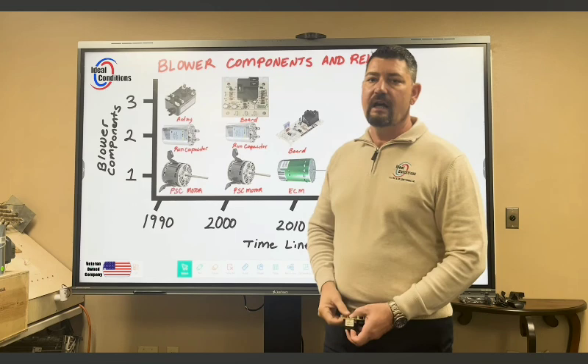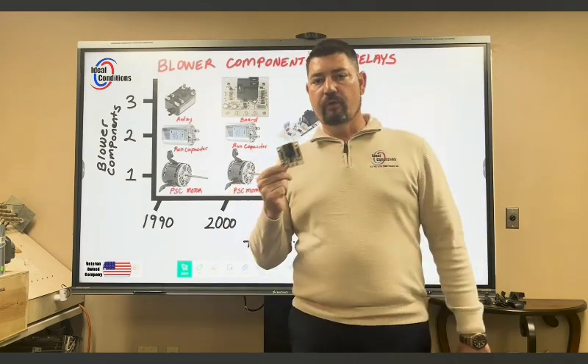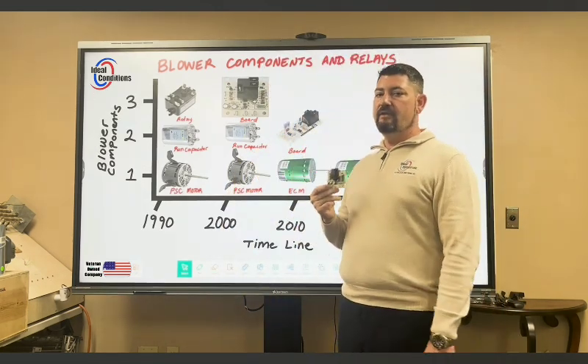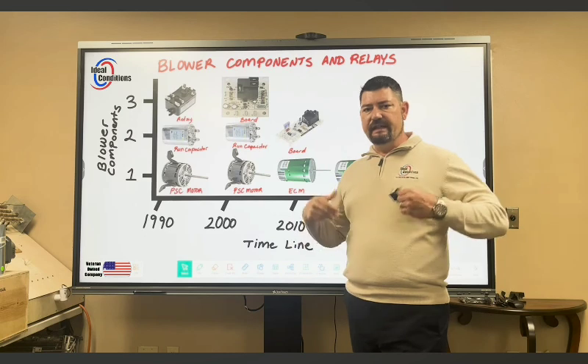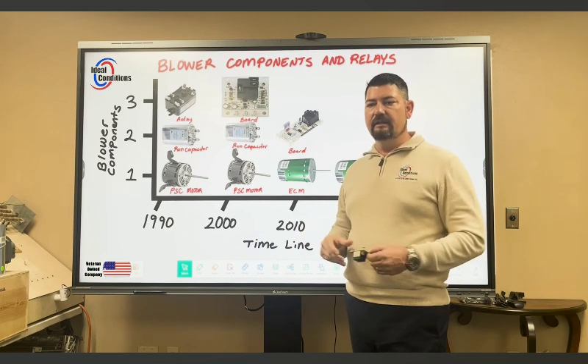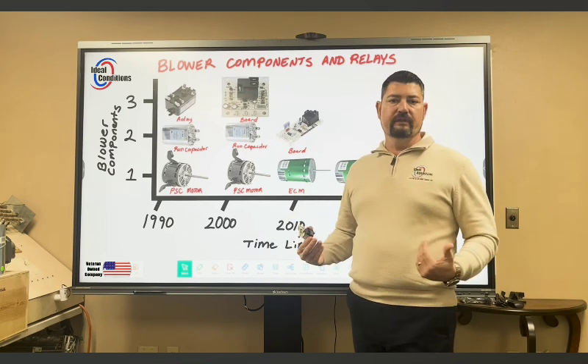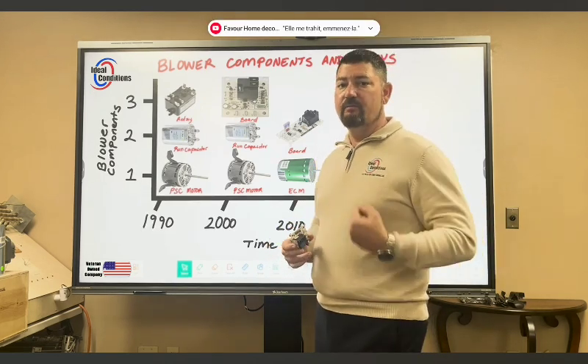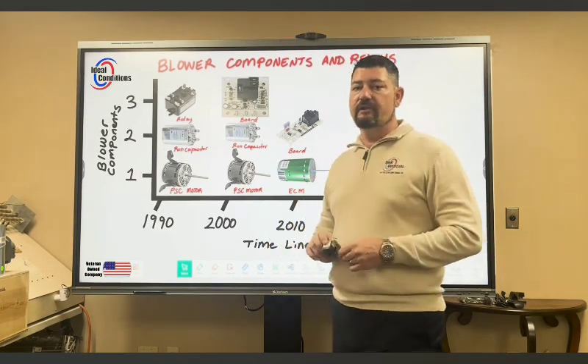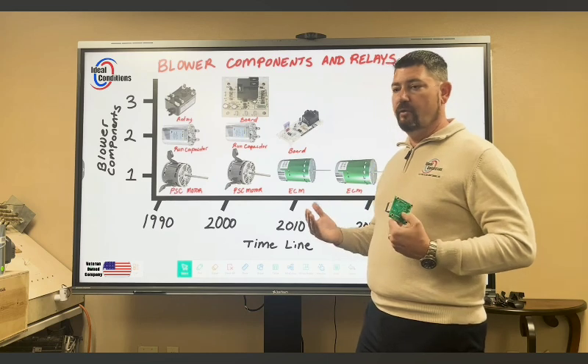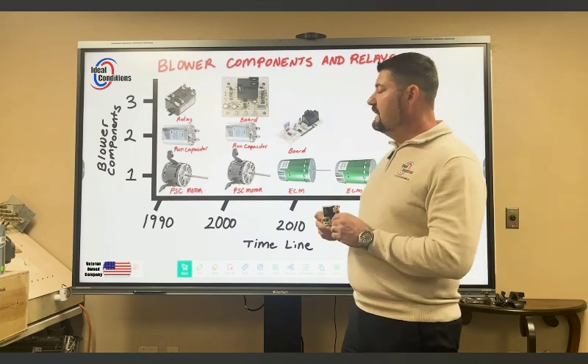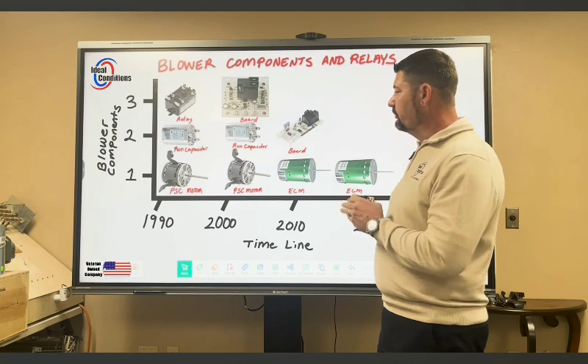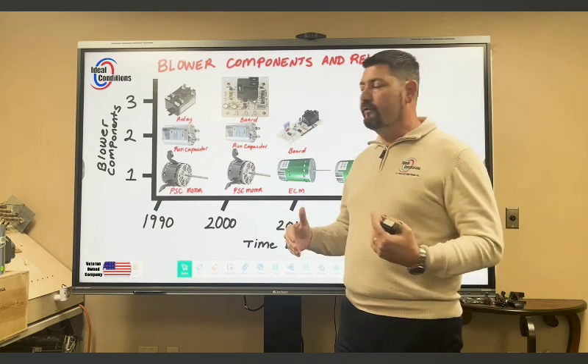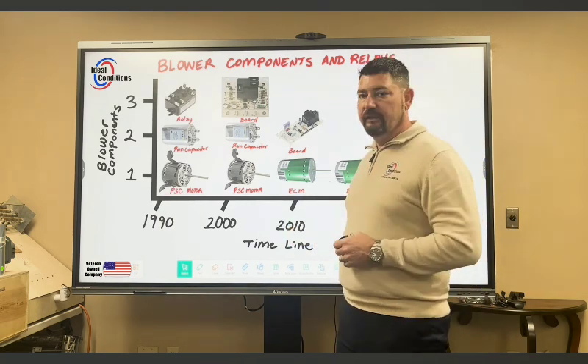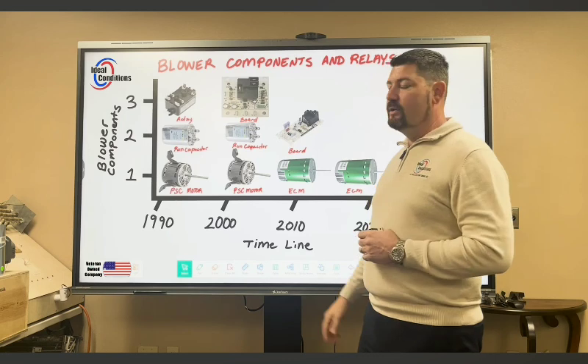However, you can still stock simple blower control boards that aren't that expensive, that give you that efficiency and that savings you're trying to get out of that unit. That coil is either warm if it's in heat mode or cool if it's in cool mode, and we can get more dehumidification, more efficiency out of that, and higher comfort if we start delaying the blower motors on an off delay. And that's the thinking behind these blower control boards. There's several different blower control boards that we're going to go over and integrate onto a PSC motor before we get into the ECM motors.